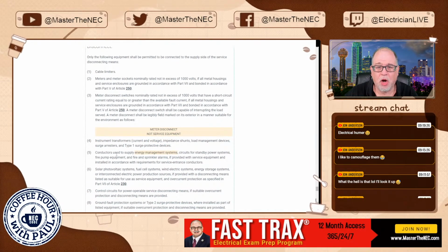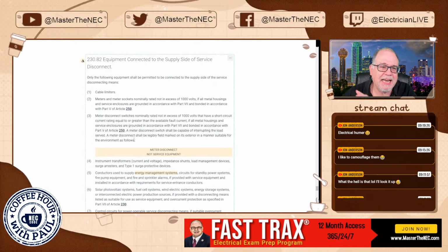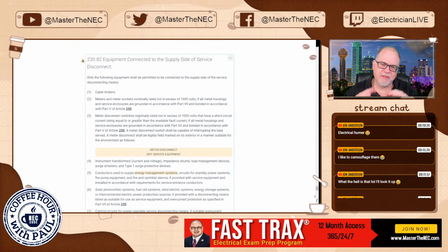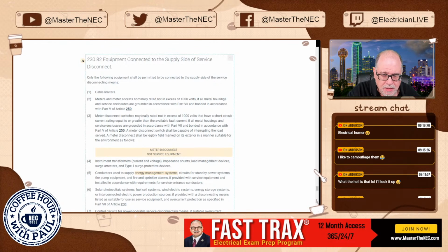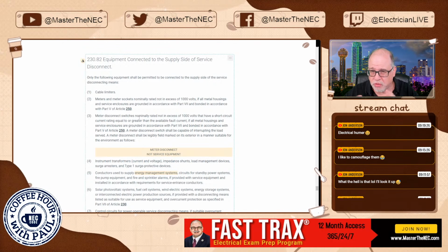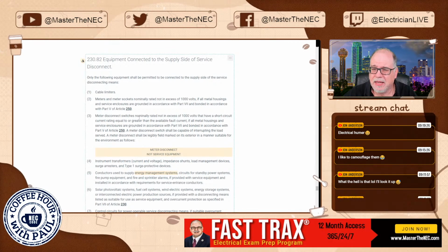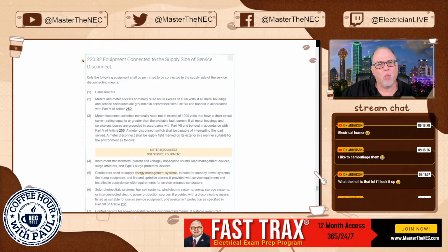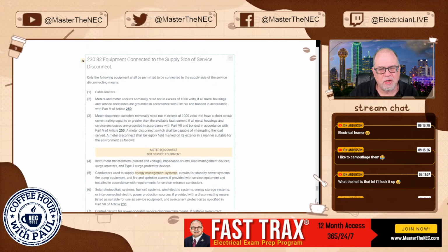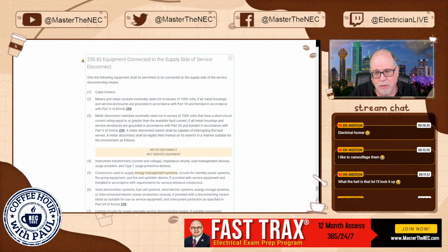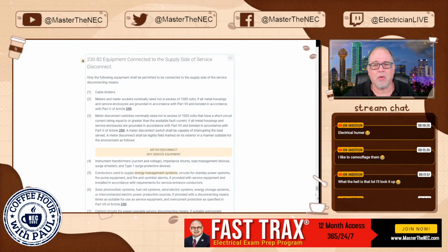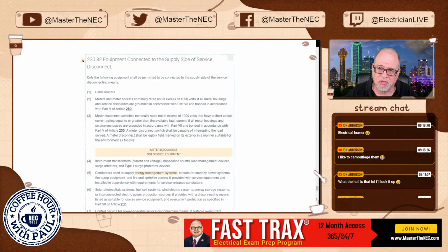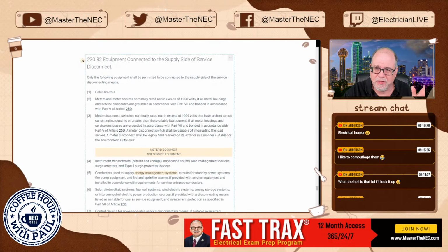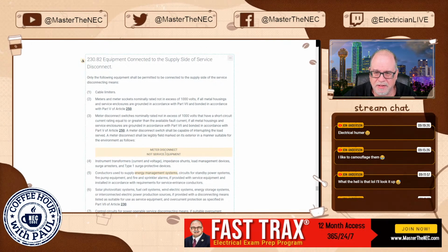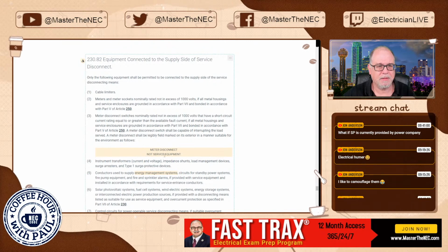All right, now also mention this. In 230.82, before I get to 85, this was the list of things that can be where? On the supply side. Well, meter disconnect switches obviously is one of those things that can be on the supply side. And now the markings that were in 230.85 that talked about it being a meter disconnect, that it's not service equipment. Well, now you have the marking requirement if you choose to use a meter disconnect switch on the supply side of service disconnect, then you're going to have to make sure that it is labeled, legible, and marked. Okay. So there you go.